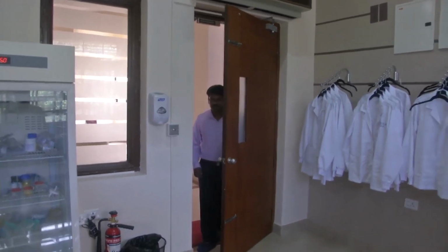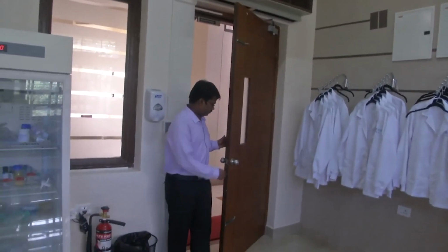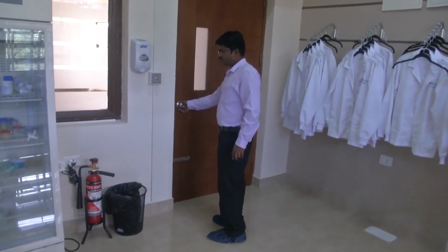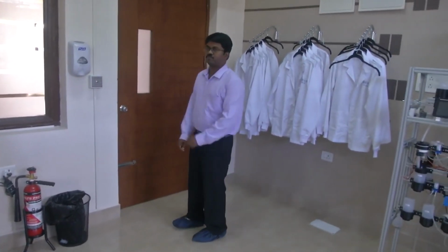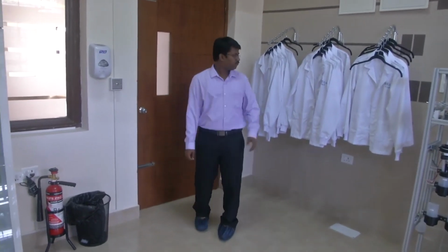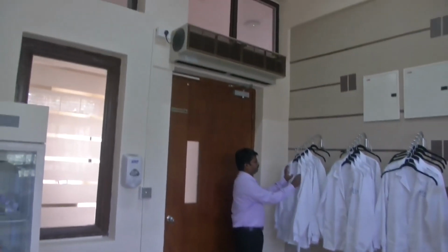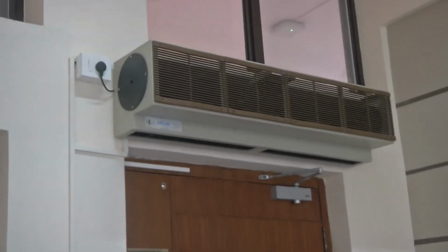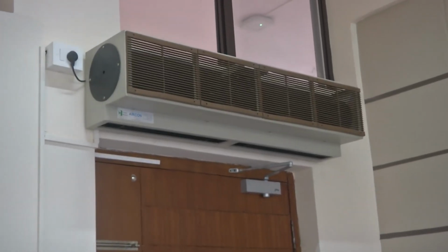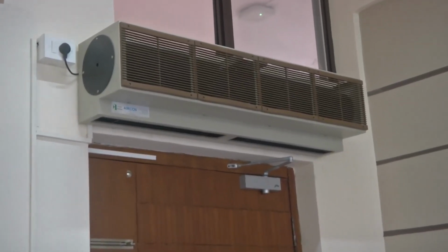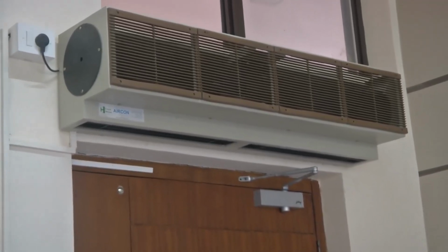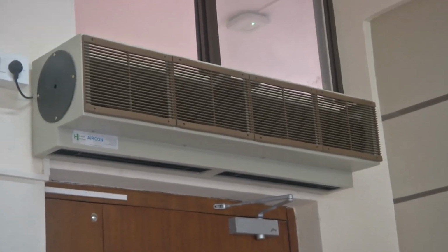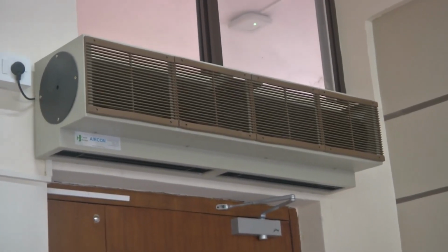So now you see how he enters the clean room and then shuts the door. The noise you saw in the clean room is the air filter. On top we have an air curtain which is going to flow air at around 10 meters per second speed.